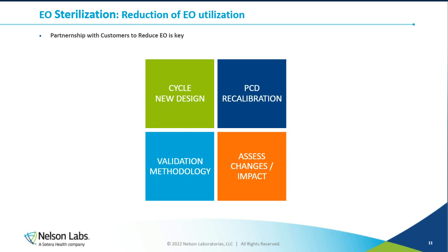The third aspect to consider is the validation methodology, because for the ones that are familiar with ethylene oxide sterilization, half-cycle overkill approach has been broadly used. Probably 97% of the validations were following the validation methodology of the half cycle. And if I'm doing the comparison with radiation, it would have been the VDmax 25 method that would be applied by default. But there are alternative approaches that can be used that can have better suited cycle that can be developed. Of course, if we are changing any of the parameters here, we need to assess the changes and to see what impact it might have on different aspects.